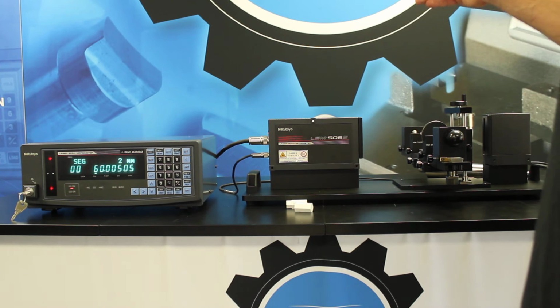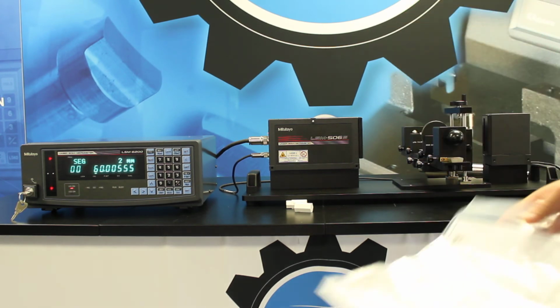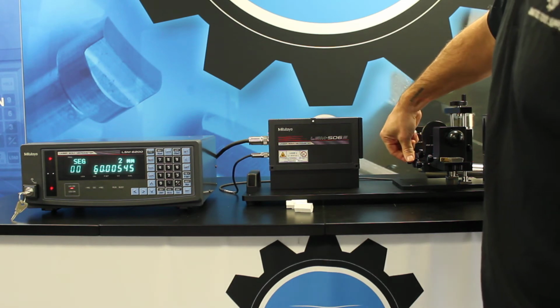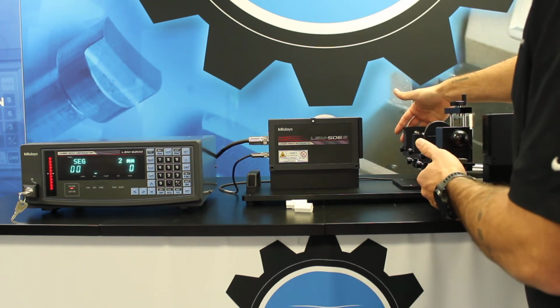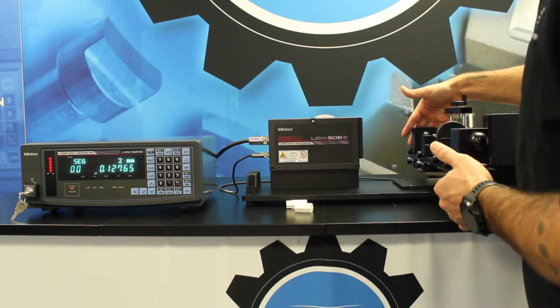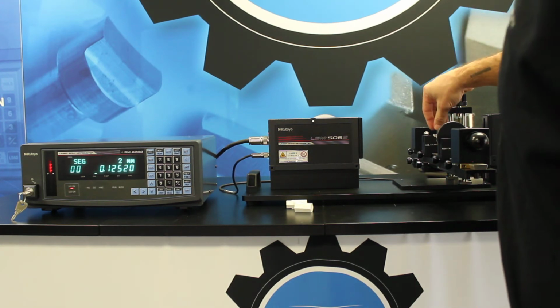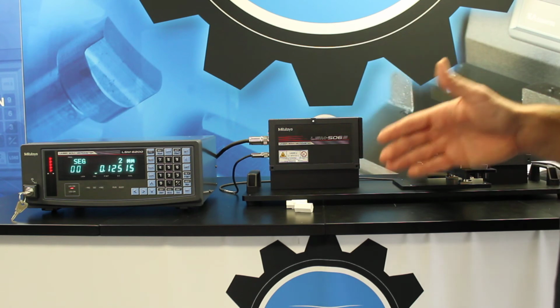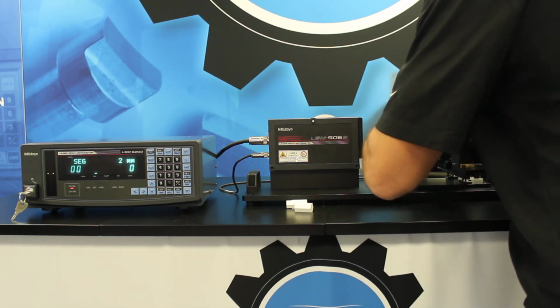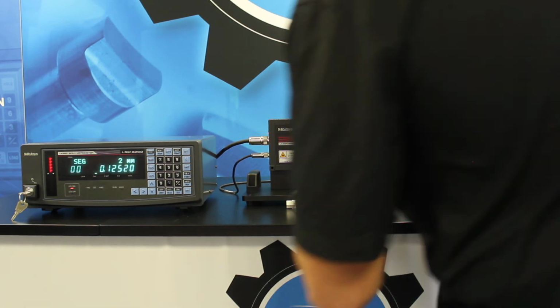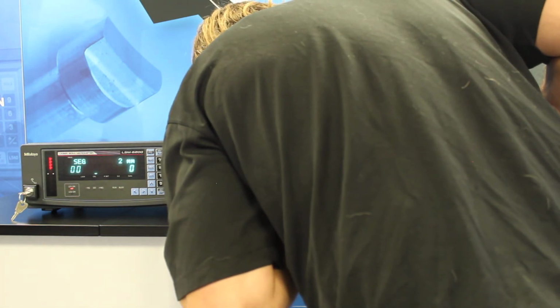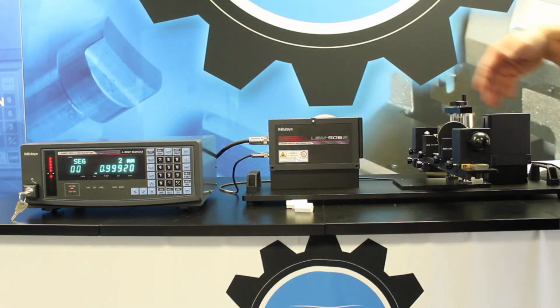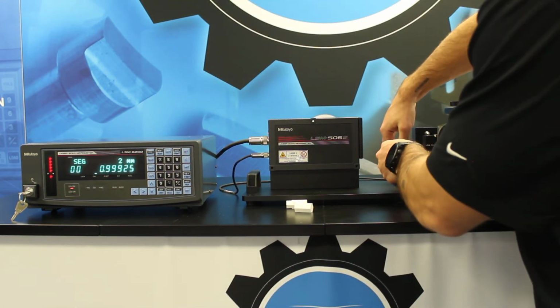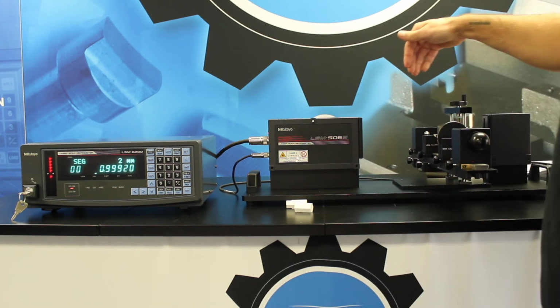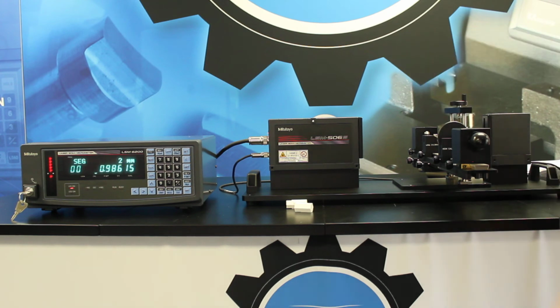Now that I've calibrated the high calibration artifact, I'm going to move on to the low calibration artifact. So the only thing I need to do is loosen my thumb screws for the rail. That's going to allow me to move the rail. I'm going to slide the rail to the point where I am in line with the low cal artifact. I'm going to make sure that that pin is perpendicular to the laser. And while I was doing that, I was also making sure I was in line with the sending and receiving unit. Once I reach that desired location, I'm going to lock the rail in place with the thumb screws.